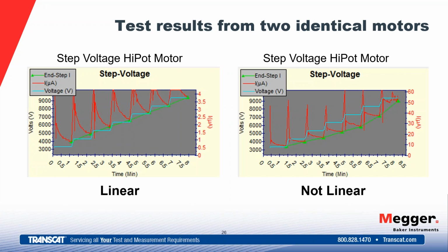So here are two examples of a step voltage test. These are identical motors, sister motors, if you will. The one on the left here, we see our step test, where the blue cyan colored line represents our voltage. As we raise our voltage up, we hold for one minute, and we're going to take a reading at the end of that one minute.